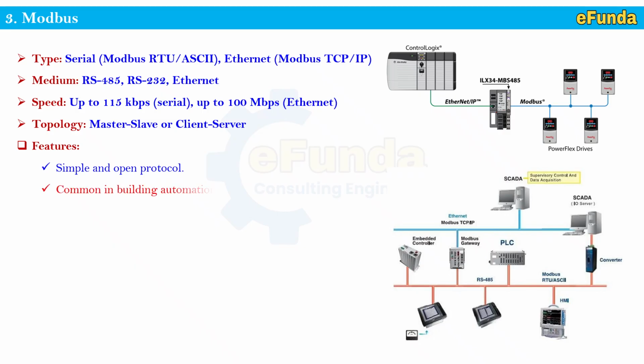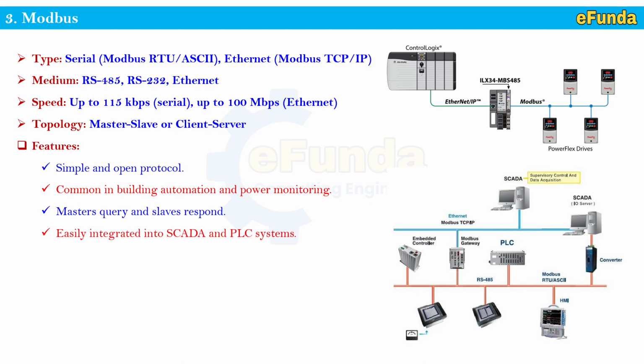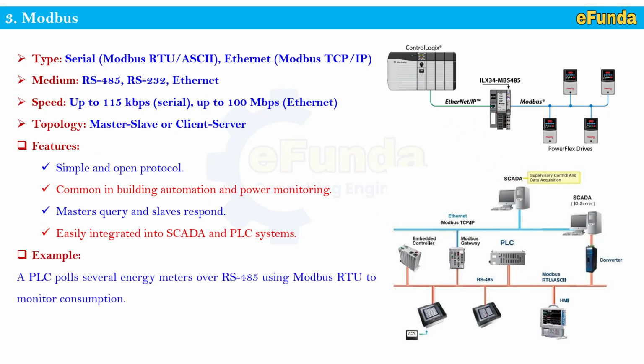Second, common in building automation and power monitoring. Third, master queries and slave responds. Fourth, easily integrated into SCADA and PLC systems. Example: a PLC polls serial energy meters on RS485 using Modbus RTU to monitor consumption. This is how the meters are connected so as to have the final integrated SCADA output for monitoring or control and data acquisition.